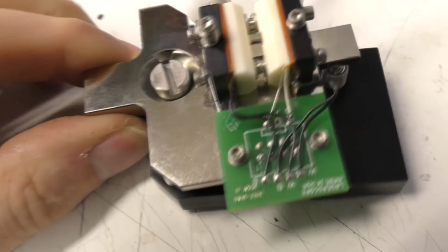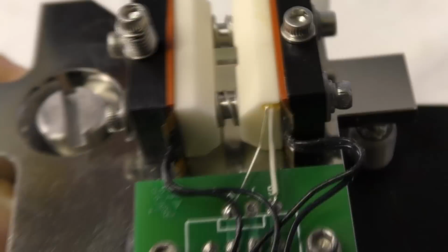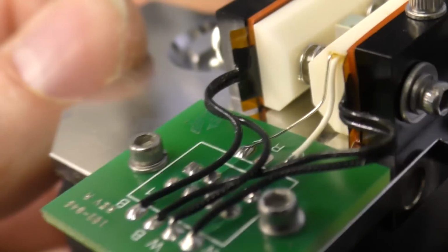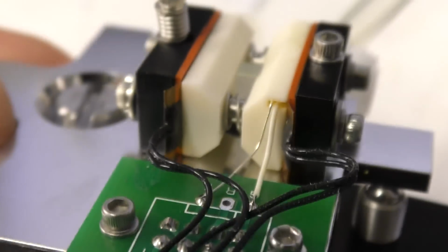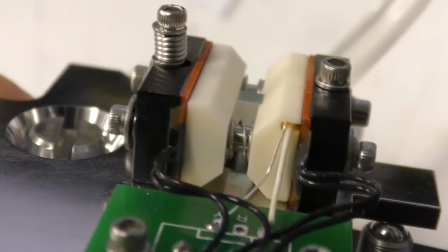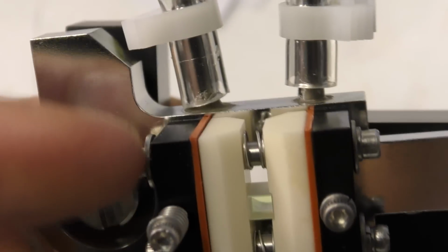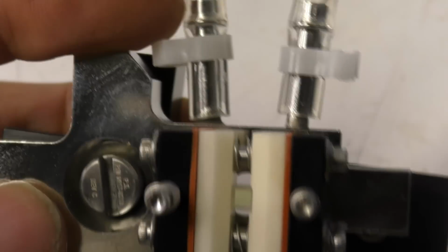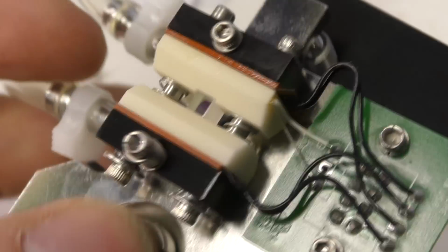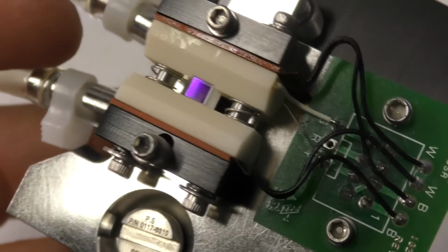A close look at the KTP holder. So you can actually see the crystal in there sandwiched between these 2 white blocks. And then there's a couple of what look like thin film heaters. There's obviously a thermal sensor there, and so those heaters are heating this up, and then the water cooling is just keeping that regulated, so it could just work the heater against the cooling to maintain a constant temperature.